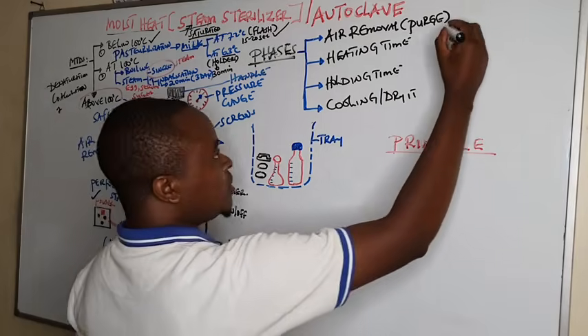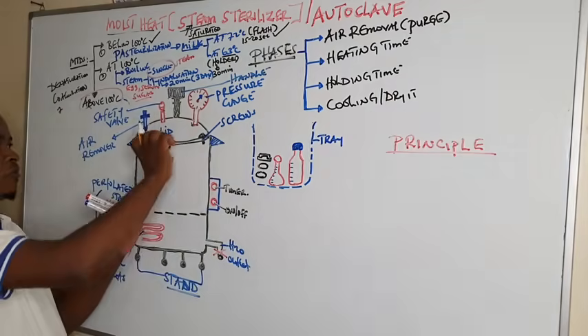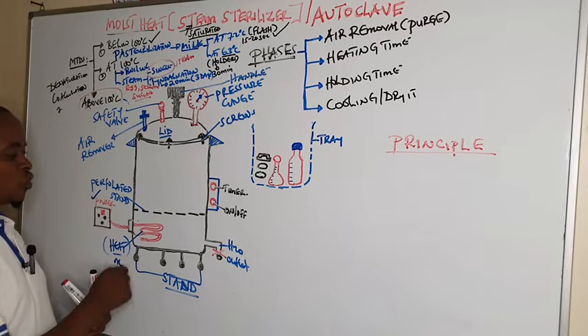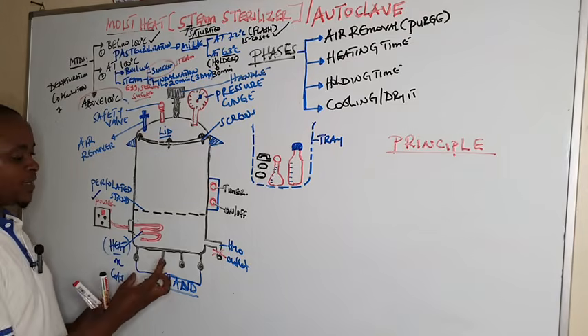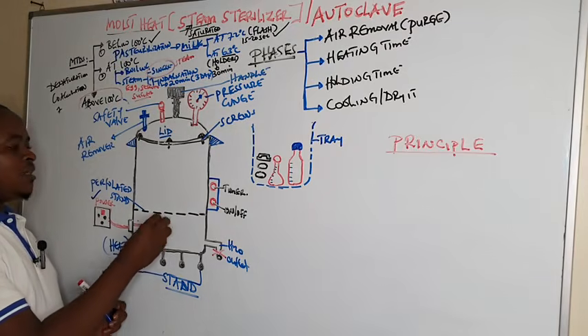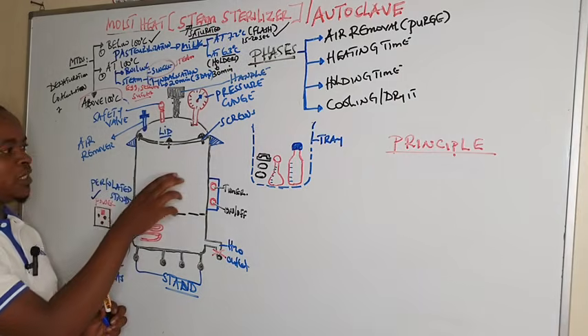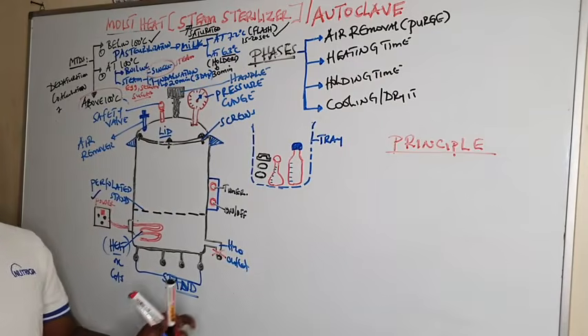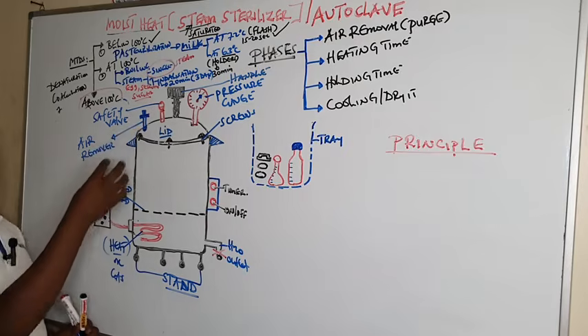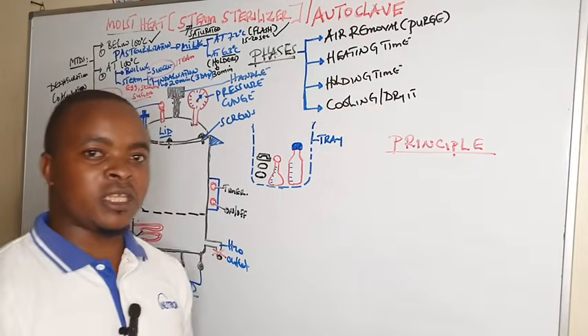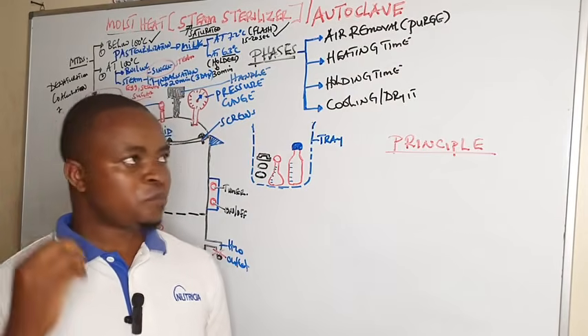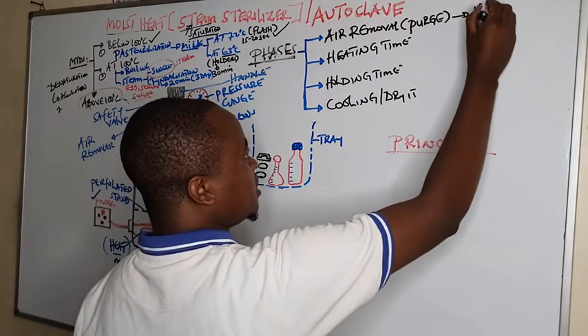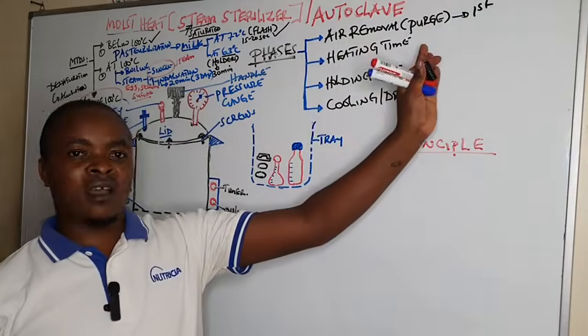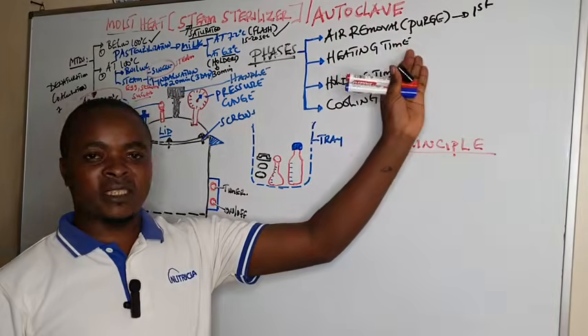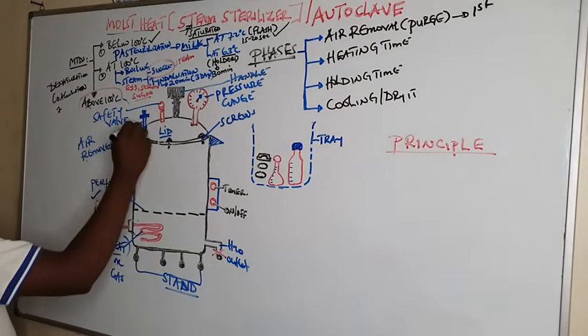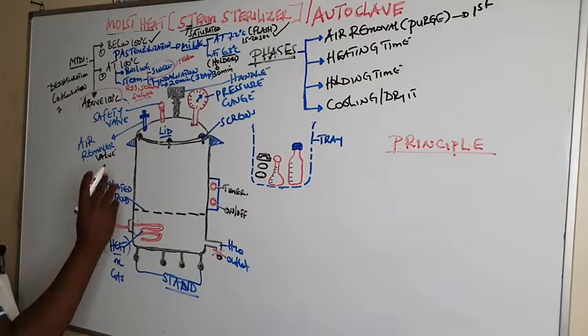Air removal comes after loading the tray in the autoclave and closing tightly with the lid, then you switch on. The first thing is that when steam is being generated by the power, the steam displaces the air which is inside the autoclave. That's why after loading, we open the air remover valve and leave it for the steam to displace the air present in the autoclave. So this is the first process in the sterilization cycle, whereby the steam being generated displaces the air inside and it passes through what we call the air remover valve. That is the initiation step.